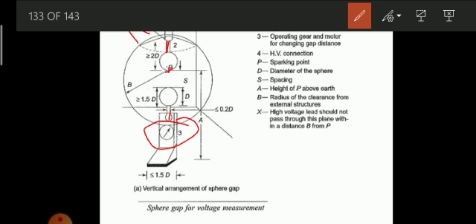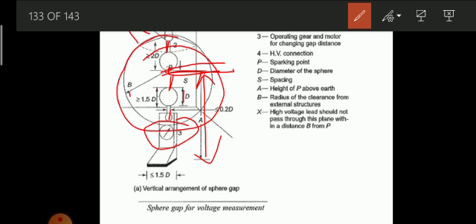D is the diameter of the sphere. S is the spacing between the spheres. A is the height of the sparking gap above ground. So A is the height of the sparking gap above earth. Next, B is the radius of clearance from external structures. It means this much has to be the radius of clearance. X is the high voltage lead, which should not pass through this plane, within a distance of B from P.